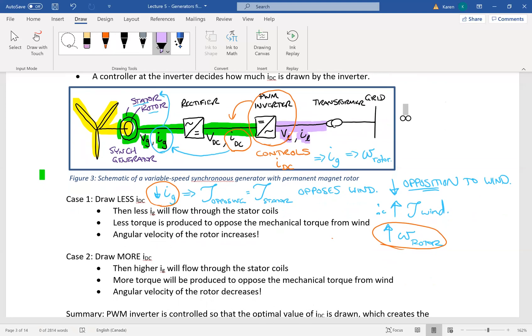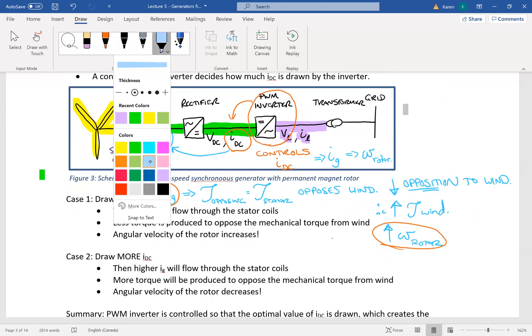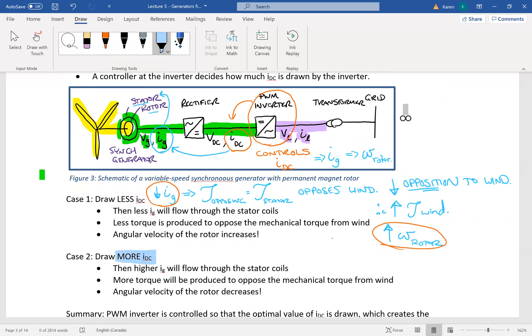And on the same principle, we could look at if we drew more current, we increase the current, then it's going to increase the flow through the stator coils, which will create more torque. And that torque opposes the mechanical torque from the wind. And if you're opposing the mechanical torque from the wind, it's going to, in effect, slow down that rotor.